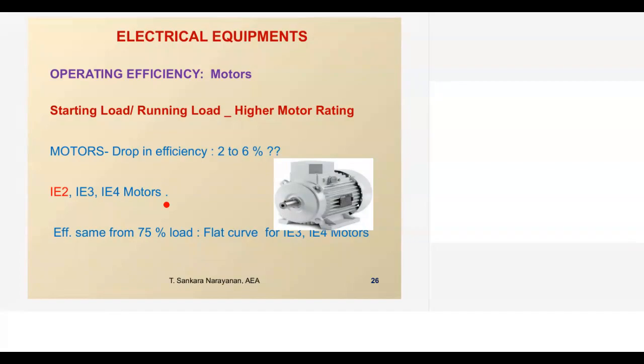So then the next utility is motors. Again, when we say motors, some of the industry senior people tell that we have 200 motors, 300 motors, so why can't we do something in the motor? So again, motor study is required in an audit. The drop in efficiency due to load can vary between 2 to 6%. Again, we will see.